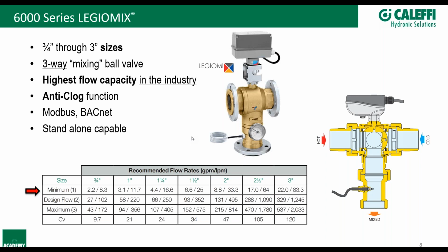But as far as how it will actually affect the whole system if people come home and start washing hands and taking showers, it really shouldn't. If you've got the secondary mixing valves, the ASSE 1070 point of use and 1016 temperature, thermal-based shower valves, things like that, you're going to be protecting those occupants. Now, obviously, by drawing off the distribution system, you're bringing in more fresh water into the system, so your boiler's got to have enough oomph behind it to keep that temperature up in the storage tank and keep up that distribution temperature as well. So it really shouldn't affect the people using it. There really shouldn't be anything there to affect them as long as you're designing it appropriately. But if you're bringing in massive amounts of cold water, the boiler might have a little trouble keeping up at that much higher temperature, which again is why the idea behind the thermal disinfection is to do it during times of very little or no demand, so the boiler does keep up.